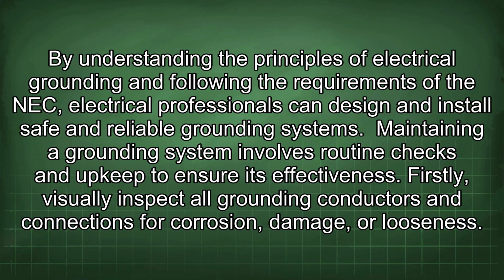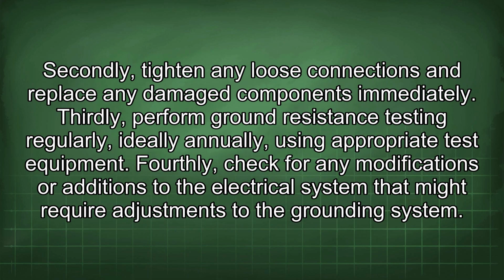Maintaining a grounding system involves routine checks and upkeep to ensure its effectiveness. Firstly, visually inspect all grounding conductors and connections for corrosion, damage, or looseness. Secondly, tighten any loose connections and replace any damaged components immediately. Thirdly, perform ground resistance testing regularly, ideally annually, using appropriate test equipment.